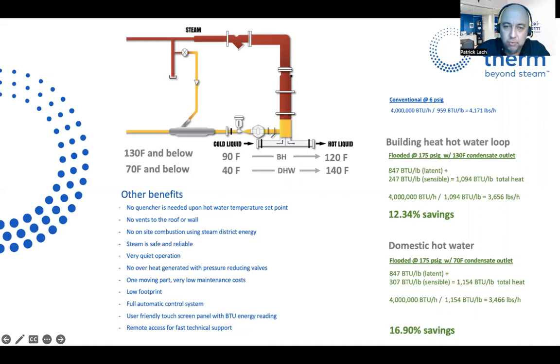And then if we go with our system at 175 PSI from Con Edison with a 120 Fahrenheit set point and condensate leaving at 130 Fahrenheit for a 4 million BTU process, you will generate 12.3% energy savings. On domestic hot water, because we'll dump condensate at 70 Fahrenheit, we're extracting more heat from each pound of steam, which is the sensible heat side. It's a big number, 16.9% energy savings when we're at full load. The other benefits around this: no quencher is needed, upon hot water temperature set point, of course.